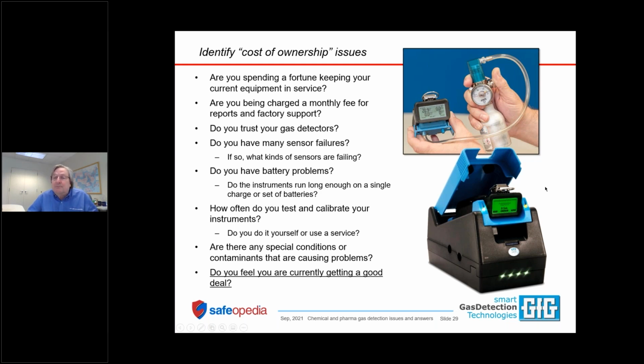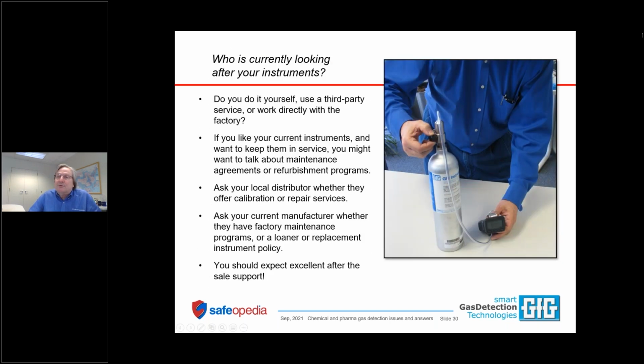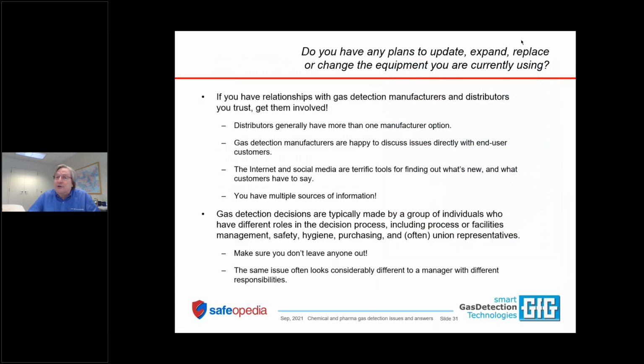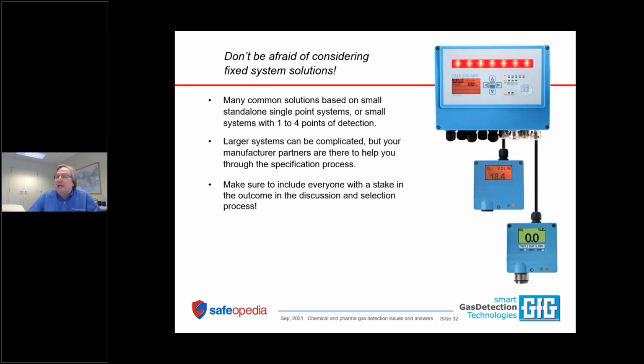It is really important. OSHA agrees, the test laboratories agree, the manufacturers agree. You should perform a bump test on the basic sensors at the very least in your instruments before each day's use. So it's going to be hard to do if you're sending instruments in once a year or twice a year to a third-party calibration service. If you agree that you need to perform a bump test before each day's use, do you have the gas that you need and the equipment that you need together with the instruments on site where you can actually perform the bump test? So once you get into all of these issues and you really think about whether you do in fact want to proceed with bringing in those new instruments, now you can bring price into the equation.